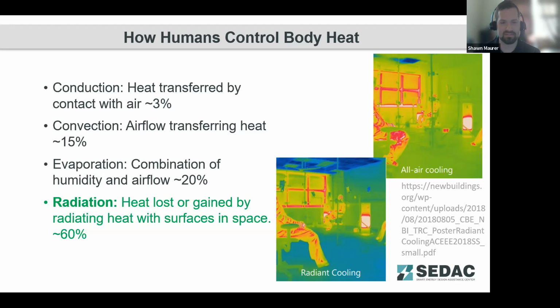When we look at radiant cooling systems, the bottom left image is a radiant cooled chilled beam type ceiling system. Where now your air systems, when you're doing ventilation and things like that, can provide more moderately tempered air. So you're not having to cool down to 50, 55 degrees. You can provide neutral temperature air, neutral humidity air. So you minimize the costs for conditioning ventilation air. And since you're providing direct cooling in that space, you also reduce ventilation for recirculated air. So some benefits of radiant systems and paying attention to the radiant environment is that you can minimize your ventilation fan sizes and improve overall comfort and temperature consistency within those spaces.